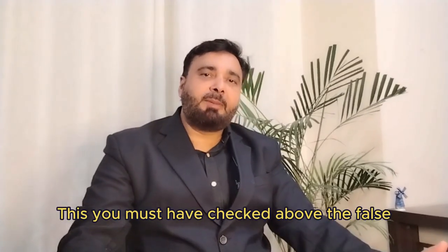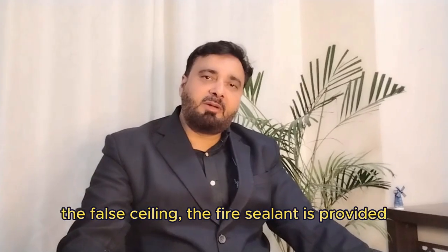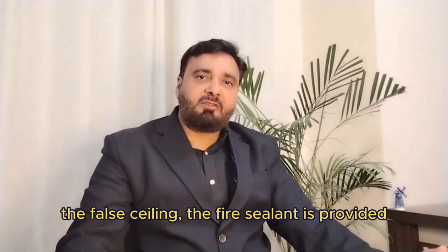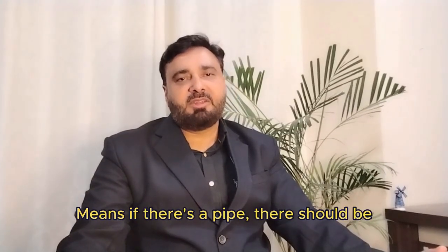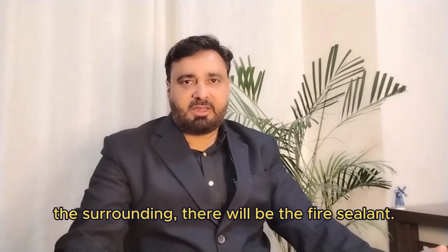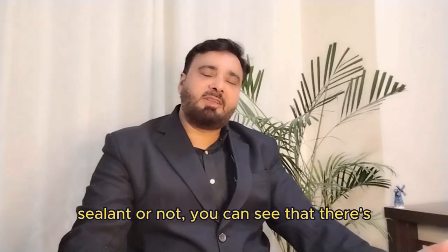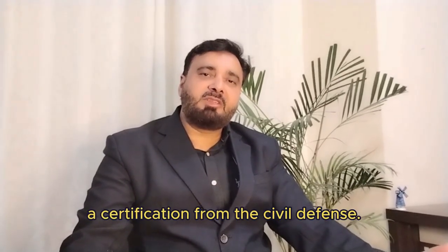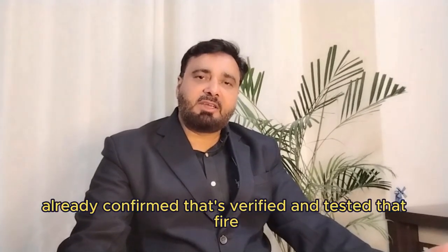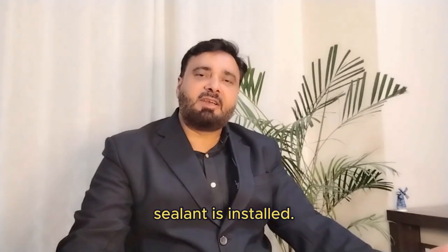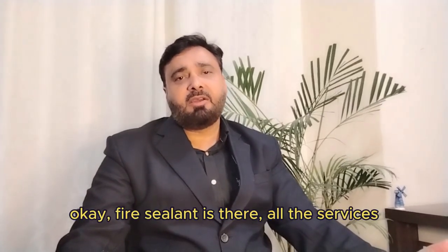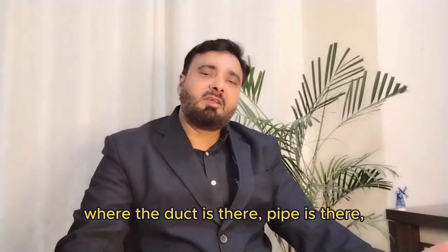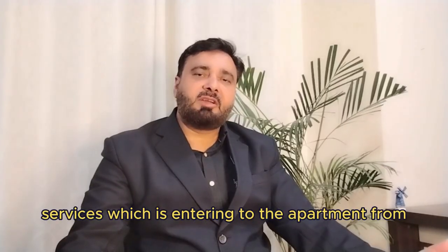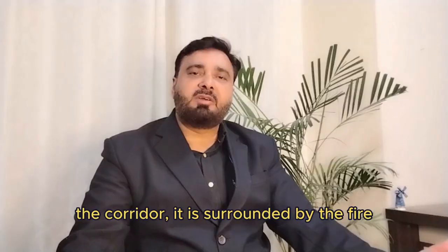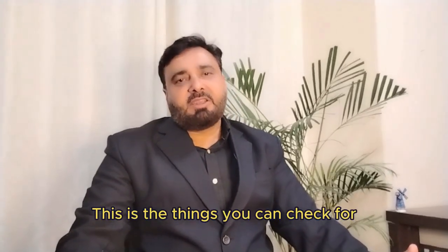You must have checked above the false ceiling, where the fire sealant is provided surrounding all the services. Means if there is a pipe, there will be fire sealant surrounding it. And how do you know whether there is fire sealant or not? You can see there is a certification from the civil defense. There is a sticker confirming that it is verified and tested and that the fire sealant is installed. Okay, fire sealant is there. All the services, whether duct, pipe, chill water pipe, or water supply pipe, which enter the apartment from the corridor, are surrounded by the fire sealant. This is the thing you can check for the fire sealant.